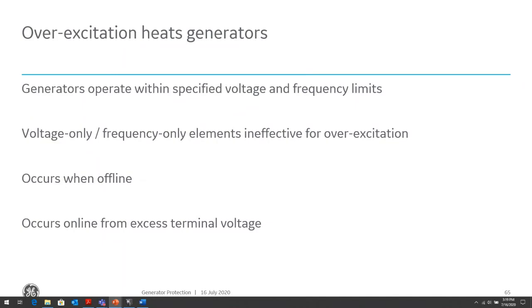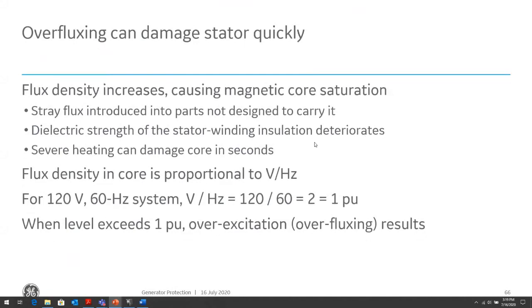So we can't just look at voltage and frequency by themselves to determine this condition. We need to look at both, and that's what we refer to as our volts per hertz protection, or overexcitation protection. We look at the ratio of voltage to hertz. If that ratio is fairly high, meaning high voltage and low frequency, then we know we have an overexcitation, overfluxing, and we can trip. This does not only apply to generators, but to any power system equipment that has a magnetic core, including transformers, where the flux density will oversaturate the transformer core and cause the volts per hertz to be elevated.